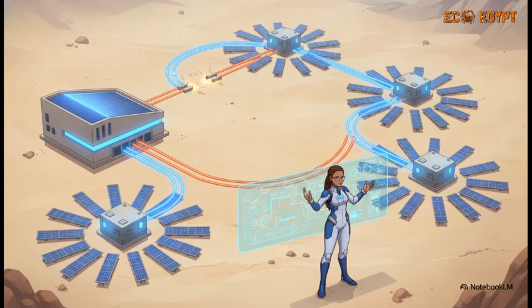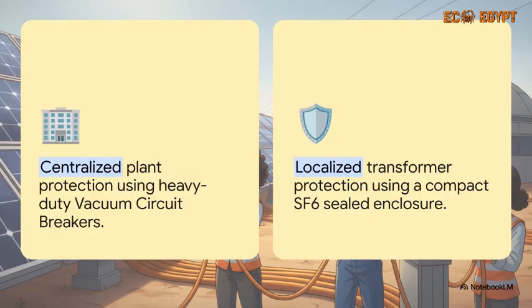If we zoom out a bit, look at how we're connecting loops back to the MV switchgear. This loop-fed configuration is just a brilliantly smart, built-in failsafe. By wiring that 33 kilovolt feed through the RMUs in a continuous loop that eventually returns to the main switchgear, you create amazing redundancy. If one specific feeder goes down for maintenance or a fault, the power simply flows backward through the alternate loop. That means you don't have to drop the entire multi-megawatt array completely offline just to service a single transformer.